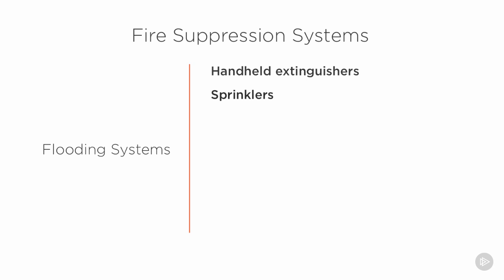In many buildings, we have fire sprinklers, and fire sprinklers could either be wet pipe or dry pipe systems. A wet pipe system means we have water right up to the sprinkler head, and usually the sprinkler head has a little glass vial that, if it gets hot, breaks the glass and it'll start spraying water. And of course, the problem with that type of sprinkler system is that it can also cause damage if the pipes ever freeze, or even if the sprinkler head itself was damaged by somebody carrying an object or something and bouncing off the sprinkler head.